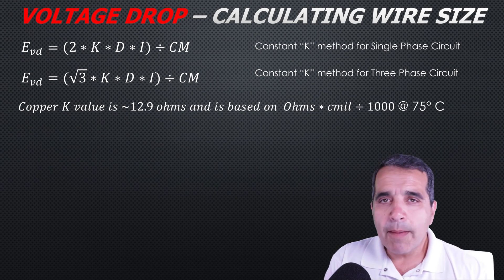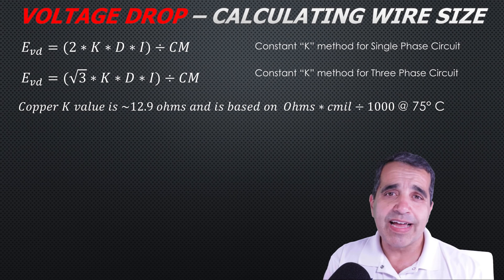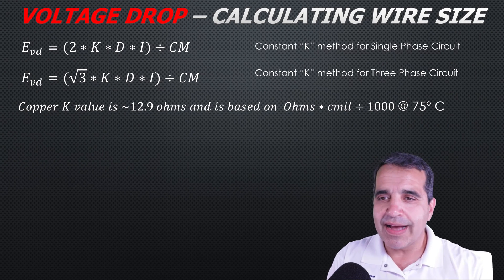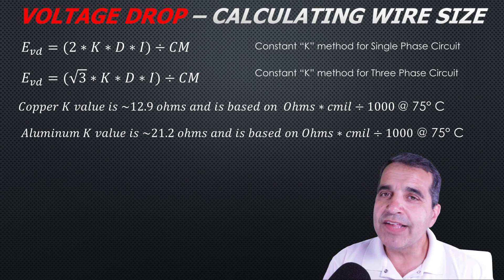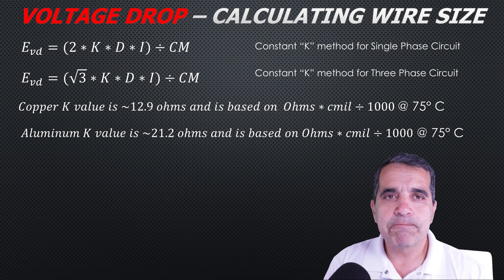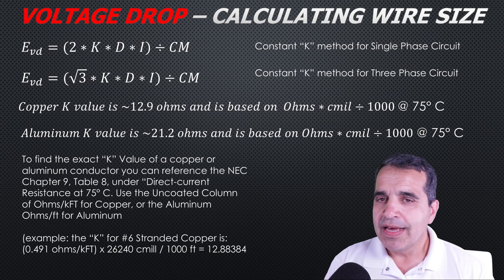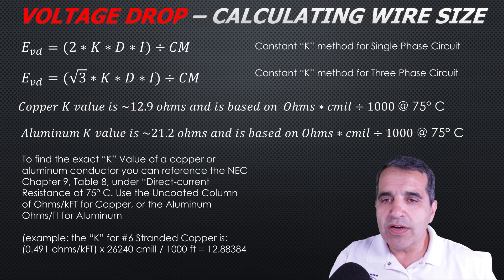The K value for copper is 12.9 ohms — based on ohms times circular mils divided by a thousand feet — calculated at the 75 degrees C column. The K value for aluminum is approximately 21.2 ohms, also expressed as ohms per circular mils divided by a thousand feet at 75 degrees C.